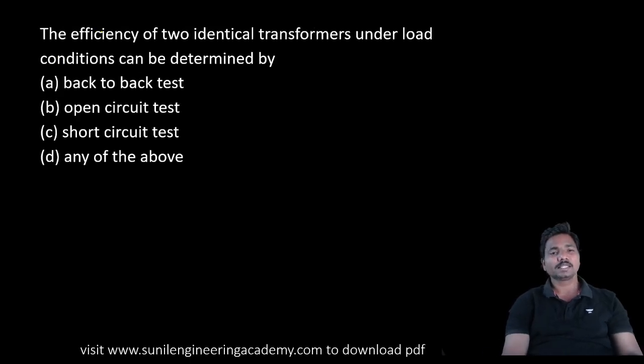Coming to the next one, the efficiency of two identical transformers under load conditions can be determined by dash. Efficiency we can directly determine by back-to-back test or Hopkinson test. So both losses we can get. So the back-to-back test is used.